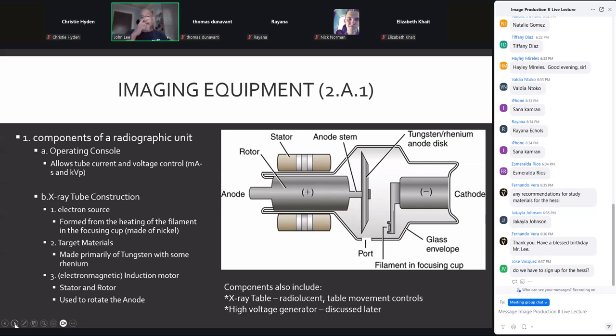So as far as the equipment goes, we make sure that we're familiar with the components that make up a radiographic unit, including the operating console, the X-ray tube, and of course our table, and especially our high voltage generator. Okay. So first, at our operating console, operating at low voltage, we have our controls for our technical factors there. We'll be able to select our tube current and the kilovoltage at the control panel, as well as turn it off, and any of the other devices that we may have at our disposal, be it fluoroscopy or automatic exposure control or anatomically programmed radiography techniquing.